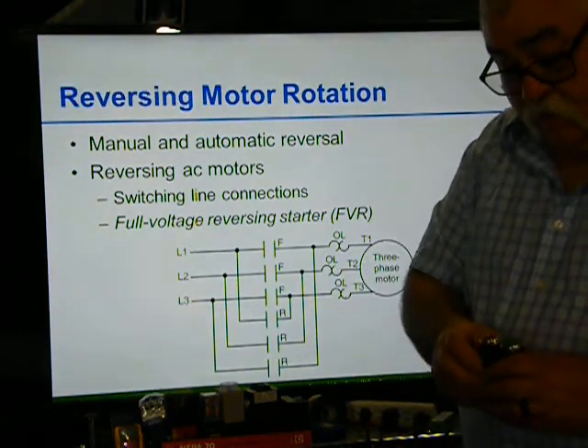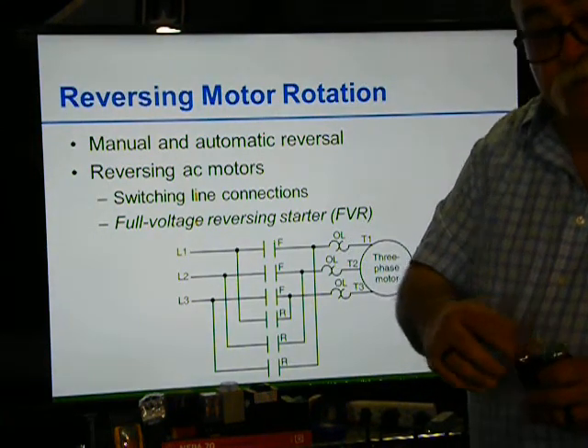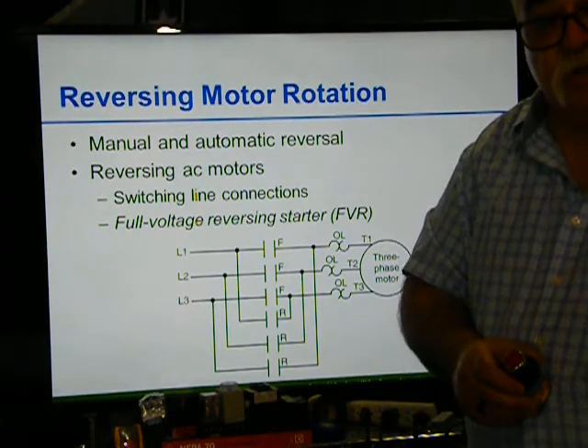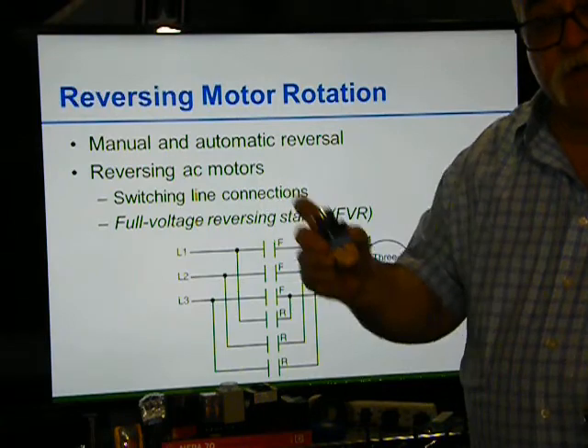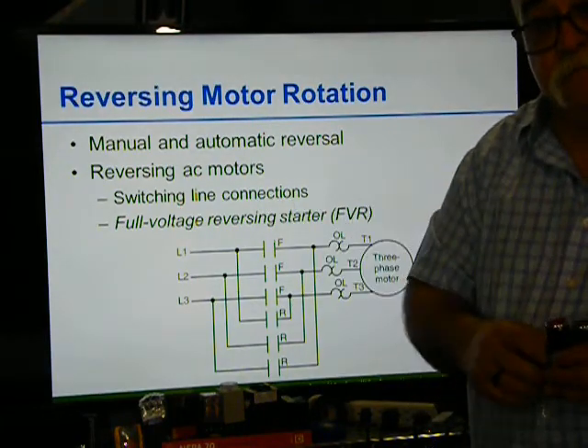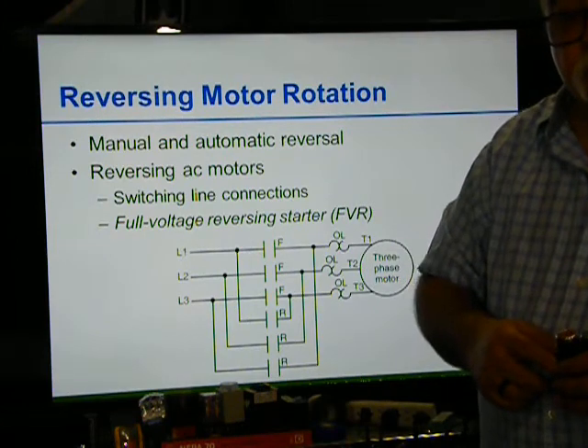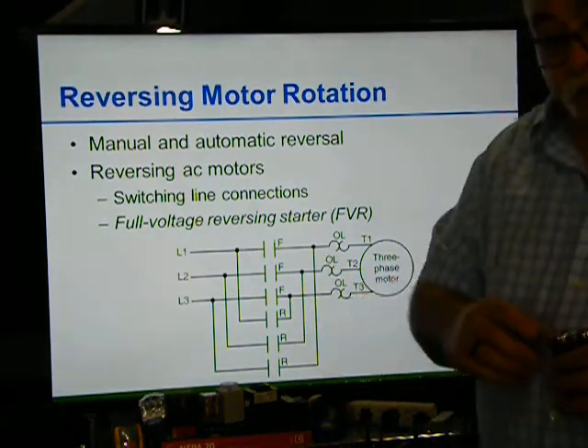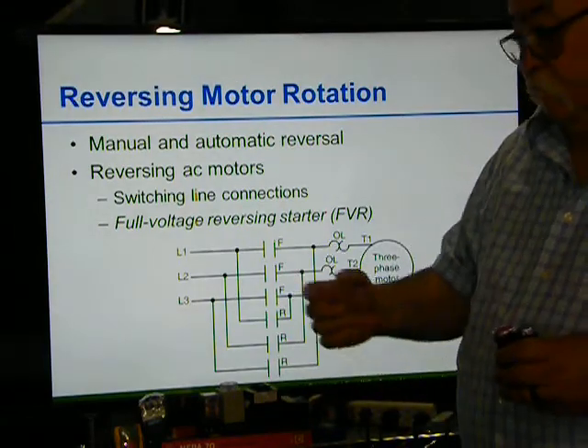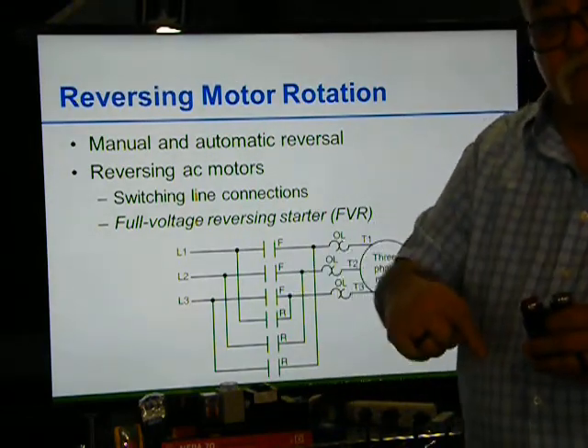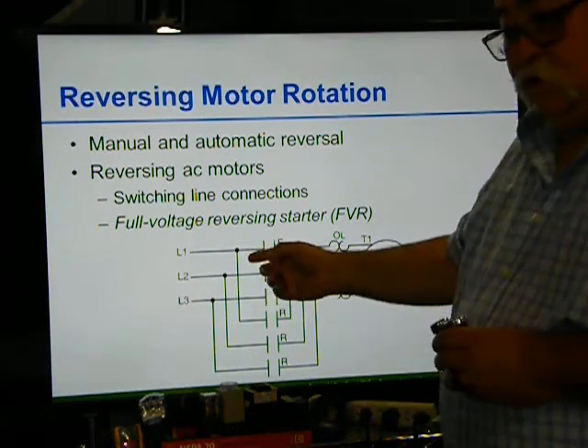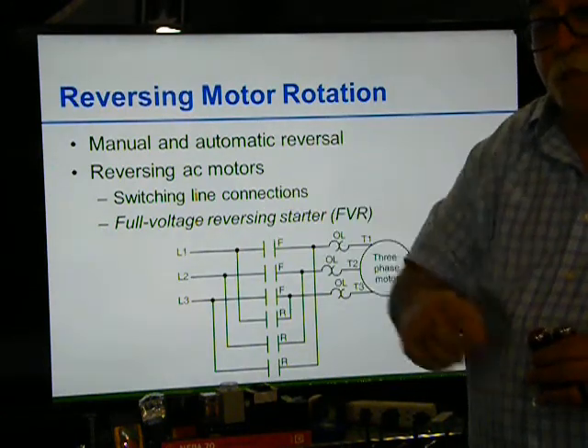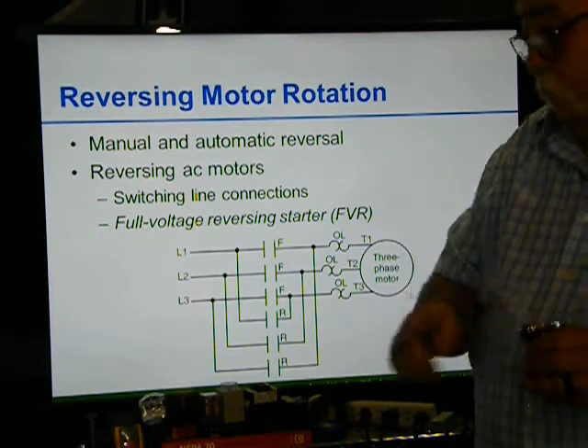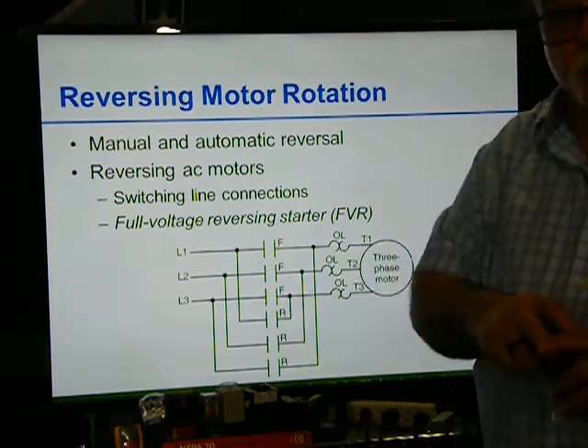The way we had it when I was working in the meat processing plant, slaughterhouse, we had a green, a blue, and a red. You hit the green to start it, and the green was forward. Go to stop, then you hit the blue button, and it would run in reverse. There was an auxiliary contact that wouldn't allow it to go from green to blue. So I had to turn it off, disconnect this, before that other button would do anything. If I hit the blue button while it was running, it wouldn't do anything. Why? Because I had to physically stop one to turn the other one on.